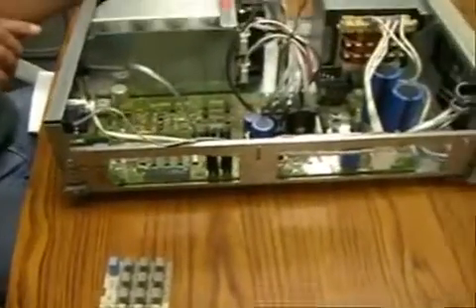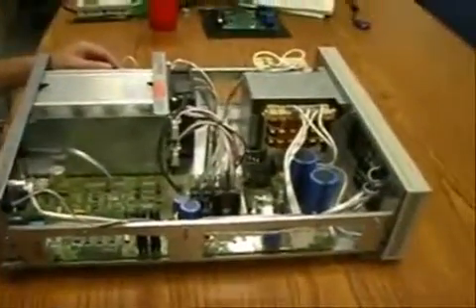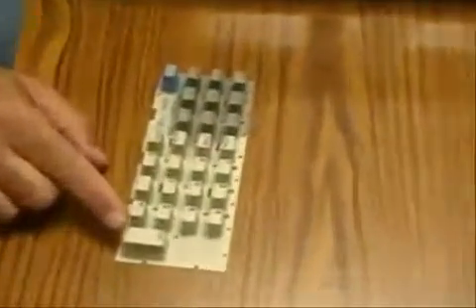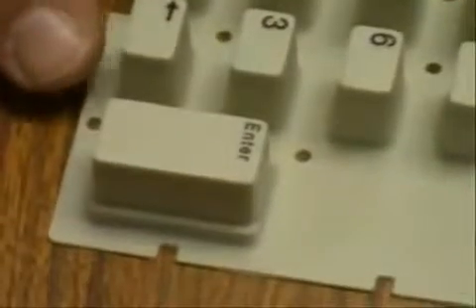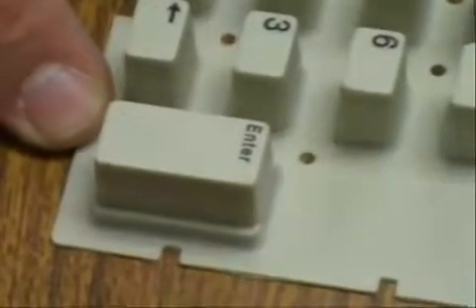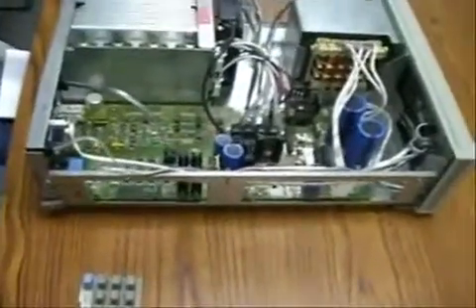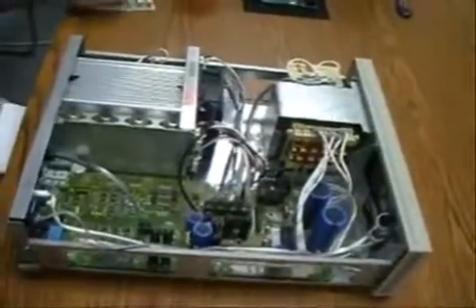The whole idea of the isolator board is to isolate the user from secondary circuits. The problem is the enter key — as you can see there's a little step in there, and if the enter key gets damaged or broken, that step makes it so you cannot get the enter key out, preventing the user from coming in contact with the secondary circuits.